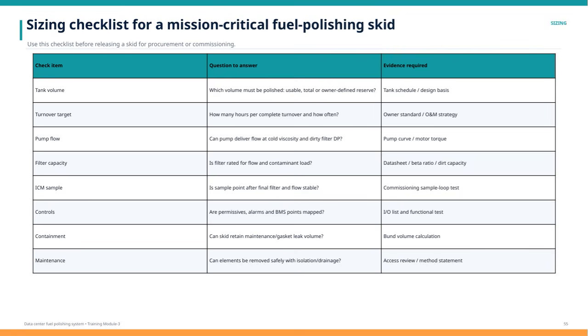Controls must be thoroughly checked. Confirm that permissives, alarms, and building management system points are mapped accurately, supported by an input-output list and functional testing. Containment is crucial for safety and environmental compliance. The skid should be able to contain any maintenance or gasket leak volumes, which you can verify through bund volume calculations. Finally, consider maintenance accessibility. Can filter elements be removed safely while isolating and draining the system? This requires a detailed access review and method statement to ensure safe procedures.